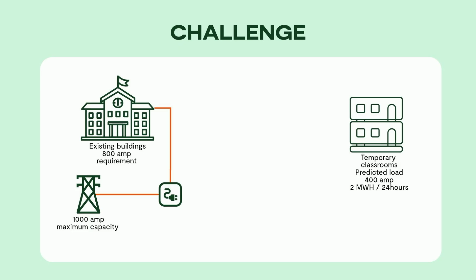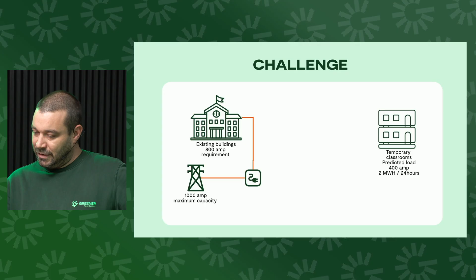So the challenge was really that on the site there was a 1,000 amp max capacity grid connection, and the existing building, so the rest of the school that was still functional, had a peak requirement of 800 amps. But the temporary classrooms required 400 amps, or around a 2 megawatt hour energy consumption over a day. But that meant that just to be able to provide the peak power, we ended up with a shortfall of around 200 amps, which presents a challenge. You couldn't just connect the classrooms to the grid because there's every chance you'd overload that connection.